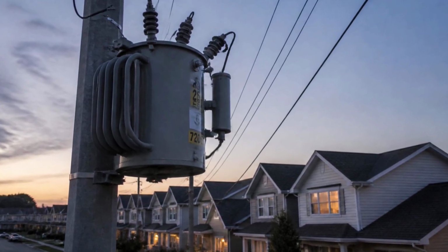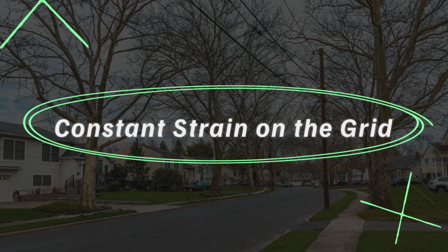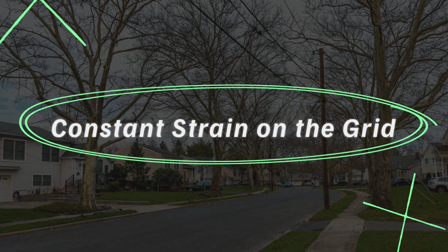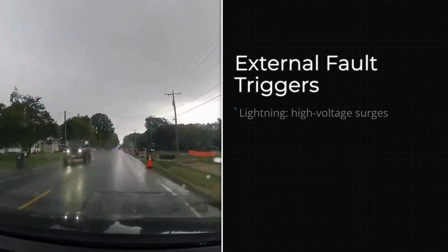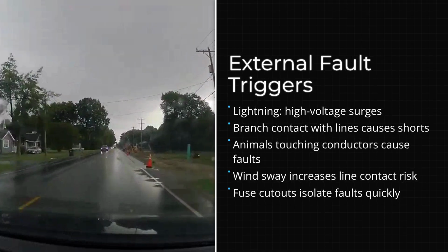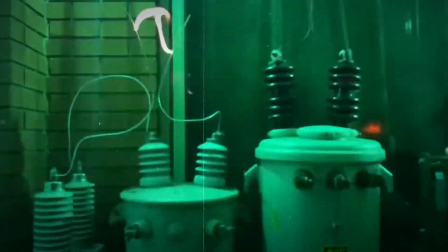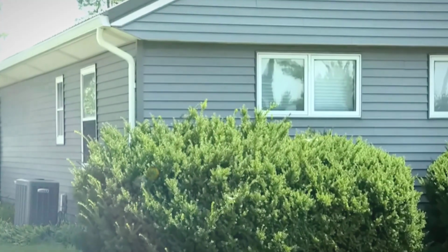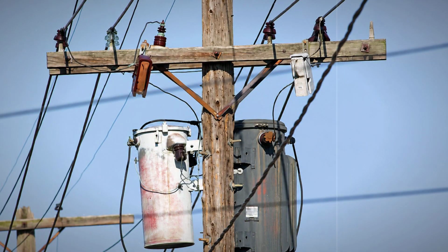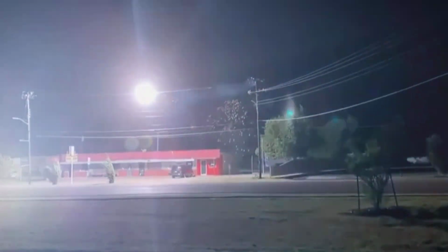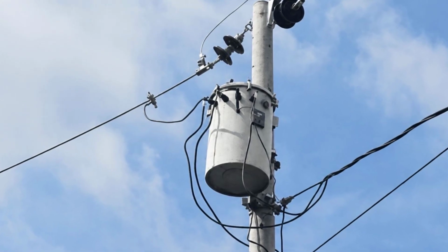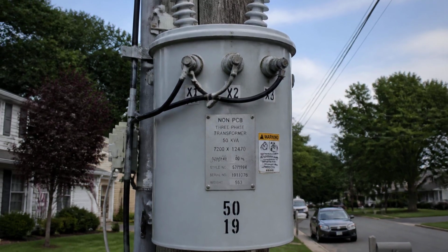grid and the home. Despite decades of reliable service, these units operate under constant environmental stress. Lightning strikes, fallen branches, and sudden animal contact can instantly disrupt the electrical balance. Extreme summer heat, overloading from high grid demand, and simple aging also take a toll, occasionally triggering an internal short circuit. When these faults occur, they are often accompanied by a dramatic flash of light or a loud, gunshot-like boom. Contrary to popular belief, this spectacular display is rarely an exploding transformer.